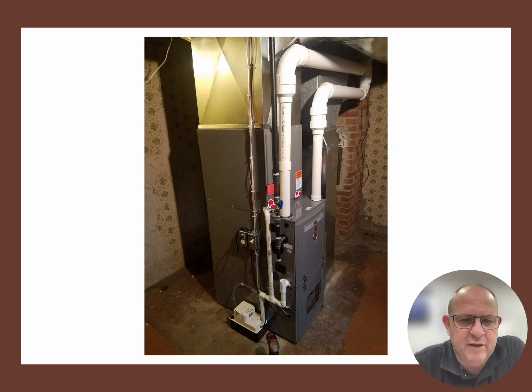Drain lines are coming down from the evaporator. We're going to tie into the furnace drain here, and notice that I have left an air gap on these furnace condensate drains so that if the condensate from the evaporator was to drain backwards into the furnace, it would have an outlet to go to before it would flood the secondary heat exchanger and possibly ruin pressure switches that are inside the gas furnace itself.